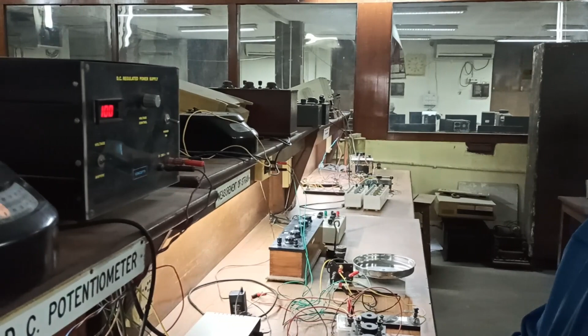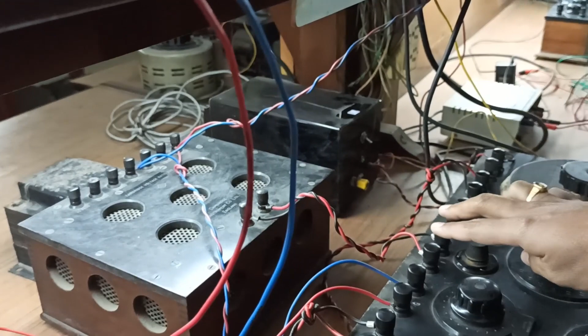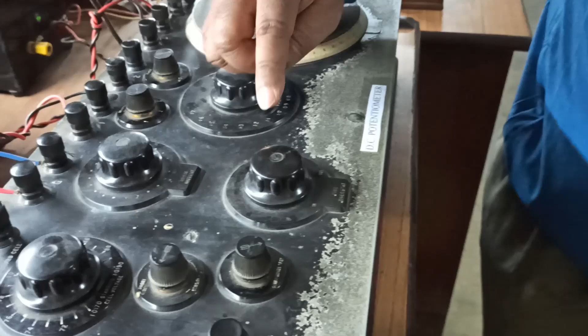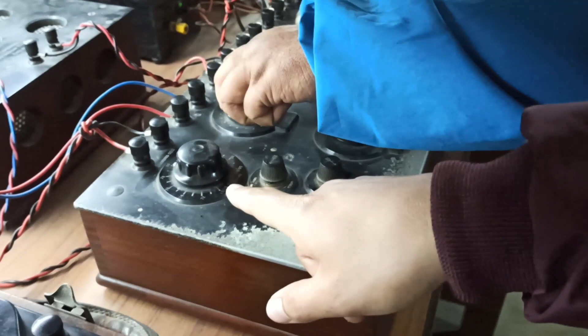So we are getting voltage supply to the voltage circuit is 100 volt, and the volt ratio box is 100 by 1. So we are supposed to get 1 volt in this DC potentiometer. So before doing the test, we need to standardize this DC potentiometer. So we are putting in this standardized mode, and by tuning this standard cell voltage and the 2 rheostat, we will standardize the DC potentiometer.